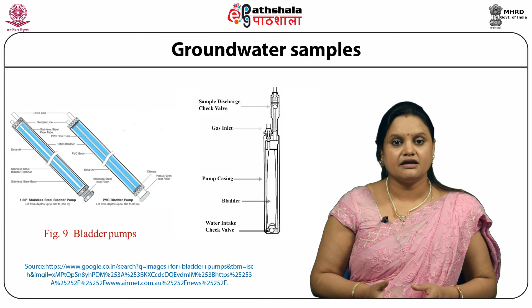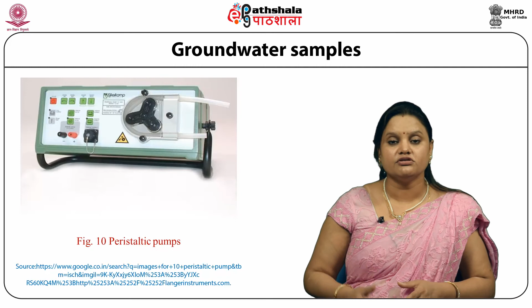Peristaltic pumps operate by a multi-roller rotating head that squeezes a rubber tube, drawing fluid through the tube. The pump tubing should be medical grade silicone rubber to avoid the organic peroxides found in other grades. Teflon connecting tubing should be used if organics are to be analyzed.